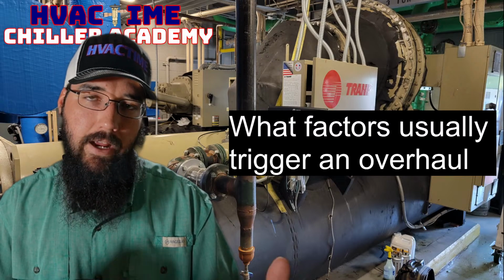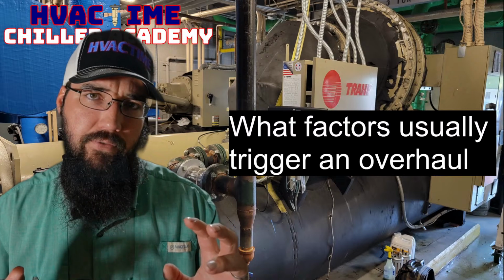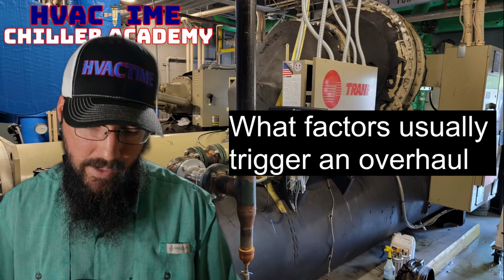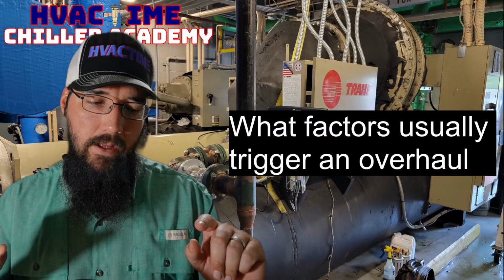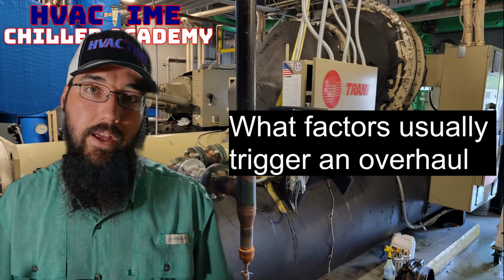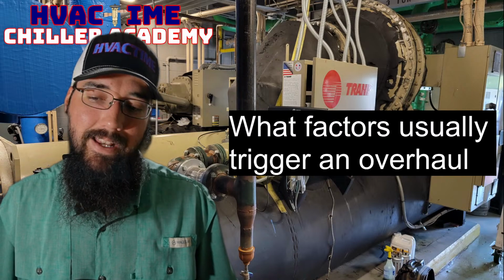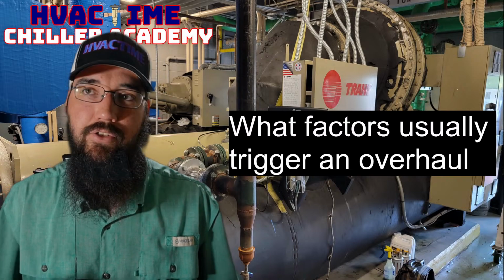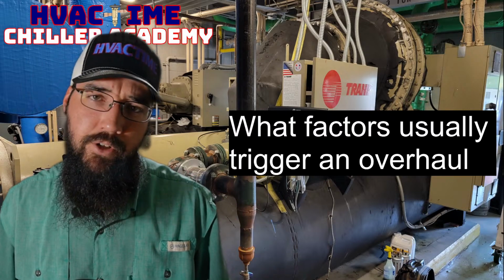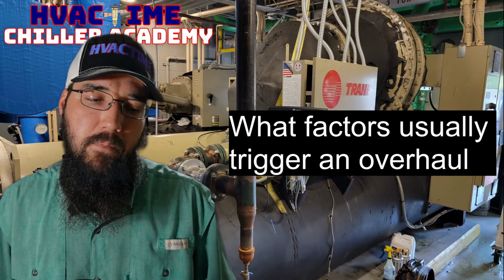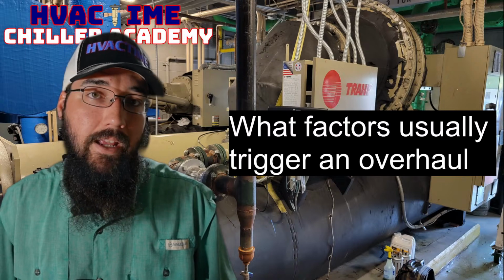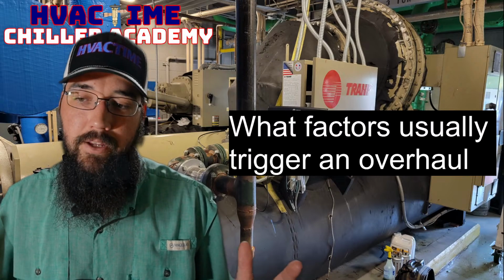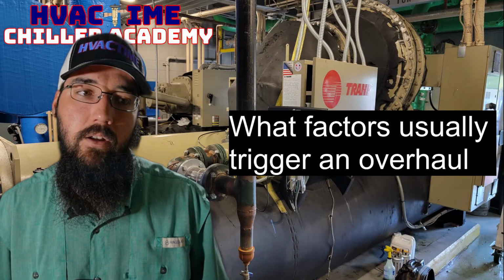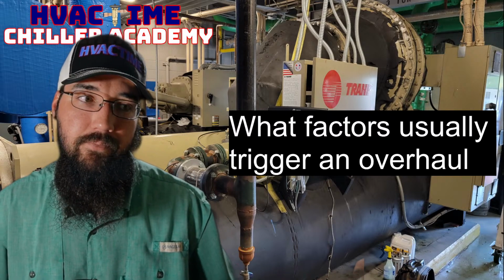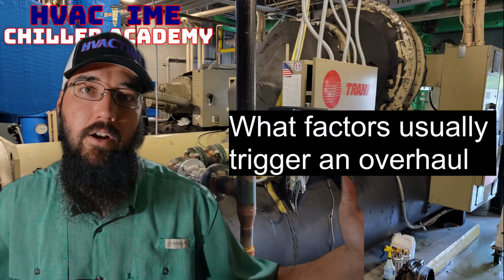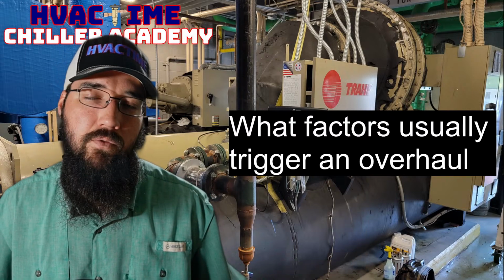So all of those would trigger an overhaul from a failure perspective. Now, there's a lot of facilities that do this on a routine basis. 60 to 80,000 hours is the industry standard for when you should do an overhaul. To be honest, there's a lot of chillers that, if treated correctly and in a proper environment, commissioned well, will run for 100,000 plus hours and never need an overhaul. They're fine.